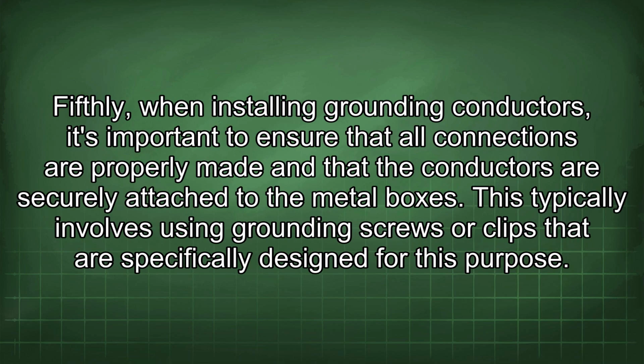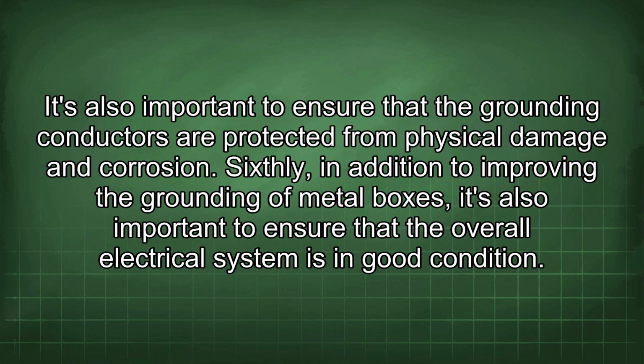Fifthly, when installing grounding conductors, it's important to ensure that all connections are properly made and that the conductors are securely attached to the metal boxes. This typically involves using grounding screws or clips that are specifically designed for this purpose. It's also important to ensure that the grounding conductors are protected from physical damage and corrosion.